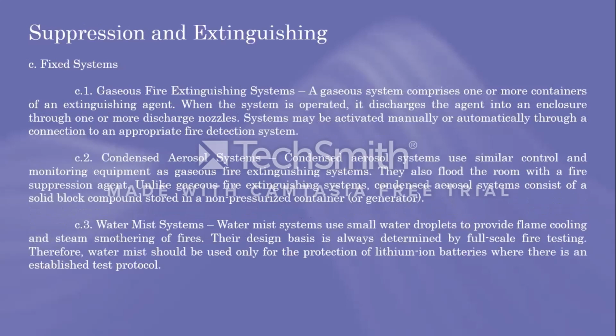So the third step is suppression and extinguishing. First, gaseous fire extinguishing systems. A gaseous system comprises one or more containers of an extinguishing agent. When the system is operated, it discharges the agent into an enclosure through one or more discharge nozzles. Systems may be activated manually or automatically through a connection to an appropriate fire detection system.